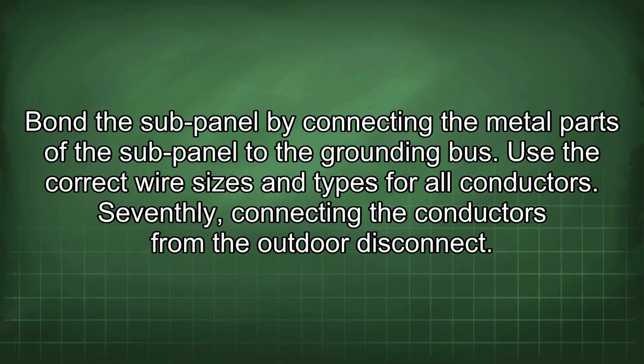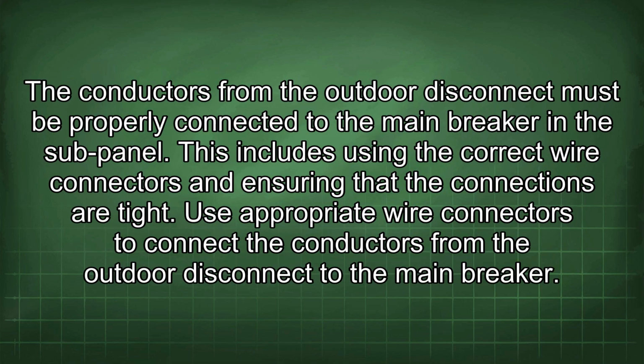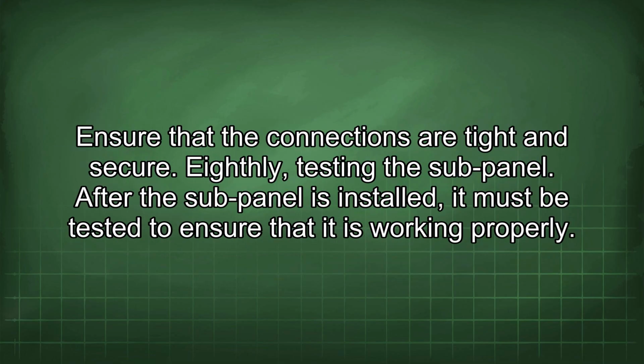Seventhly, connecting the conductors from the outdoor disconnect. The conductors from the outdoor disconnect must be properly connected to the main breaker in the sub-panel. This includes using the correct wire connectors and ensuring that the connections are tight. Use appropriate wire connectors to connect the conductors from the outdoor disconnect to the main breaker. Ensure that the connections are tight and secure.